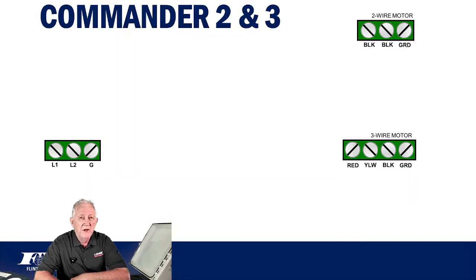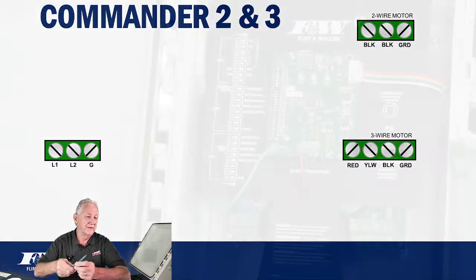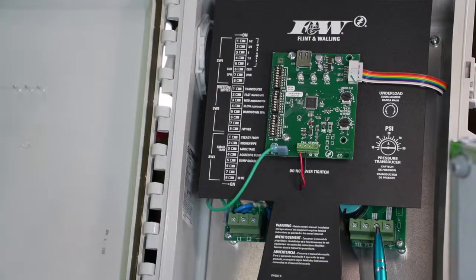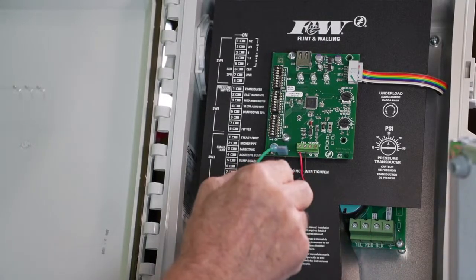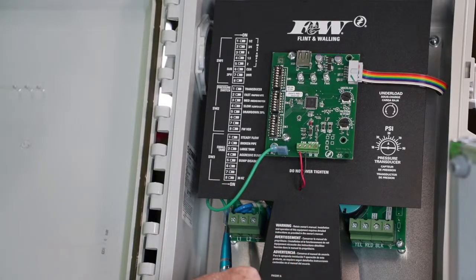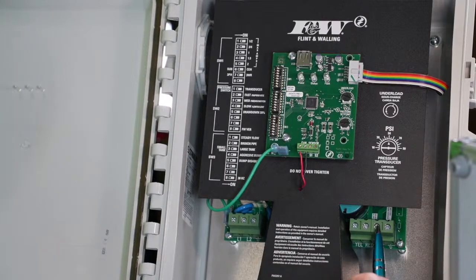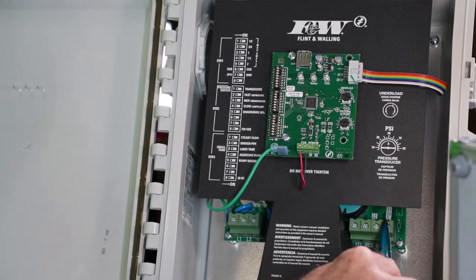Now, when we look at wiring this drive, from a standpoint of installation, you're going to bring your pump cable and your power cable in through the bottom ports of the drive. If you look at the drive, I've got both pictures here. There's this terminal block here, and this is where your pump cable is going to be going out to the pump and motor. Your power coming in will be over here on this left-hand side. These terminal blocks are very, very well labeled: L1, L2, and the ground. Again, this is where your power will hook up. And then over here is where you're going to take the cables out to the pump motor itself.